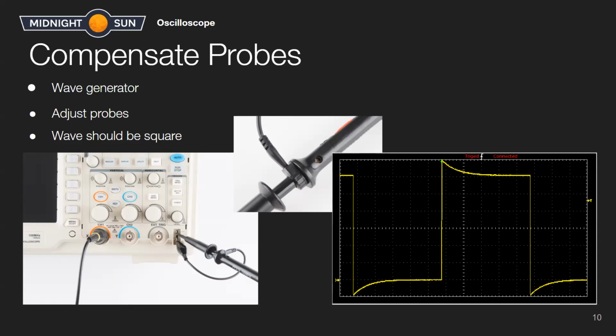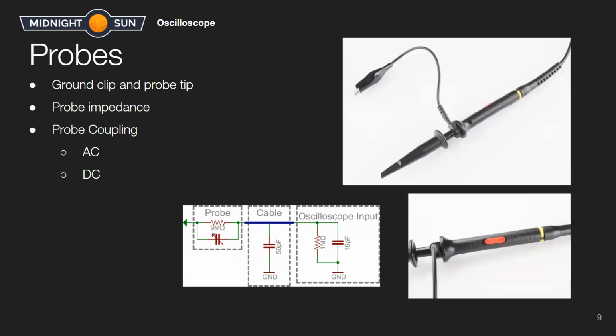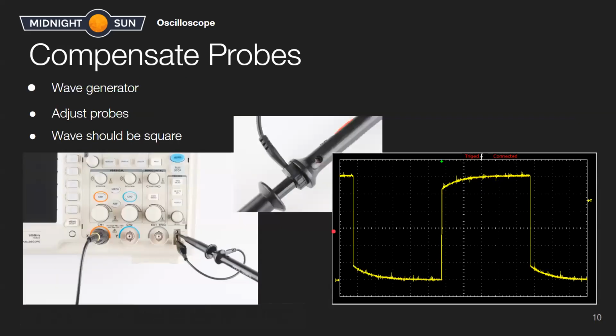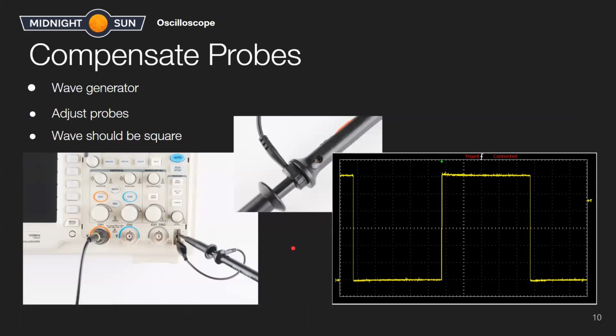Yeah, you should do this anytime that you're picking up a new probe or changing a probe from one channel to another, because going back to this image, every channel will have a different parasitic capacitance or slightly different impedance, and same with the cable and same with the probe itself. So anytime you're using a new probe or a new accessory or a new channel, you should technically recompensate the probes. Although in most cases, it probably won't change your measurement that much, but if you want it to be accurate, you should do this.